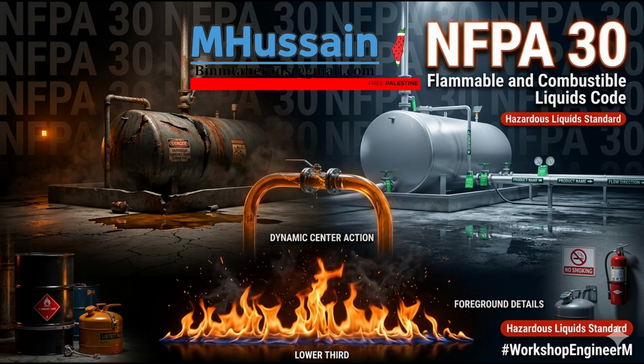A plastic container that melts releases its liquid onto the floor, making a large, spreading pool fire. But a pool fire is a two-dimensional, predictable engineering problem. We know exactly how a pool fire behaves. We can build physical dikes and drainage trenches to dictate exactly where that burning liquid flows. We can calculate the exact density of low-expansion foam needed to smother a two-dimensional surface area. But a rocket-propelled steel drum destroying your ceiling infrastructure, that is a chaotic, three-dimensional catastrophe. You cannot engineer a sprinkler system that survives an artillery strike.